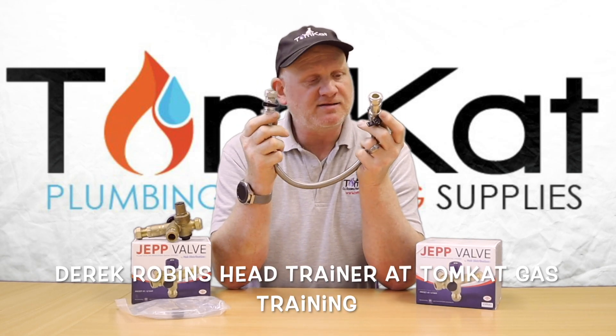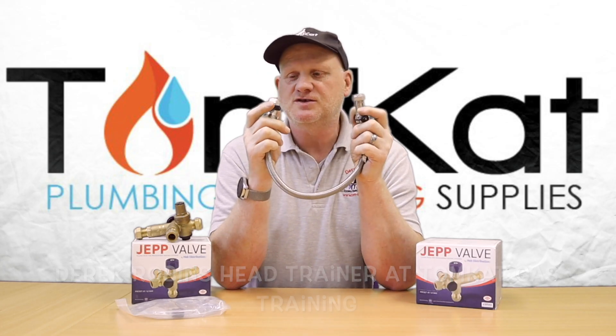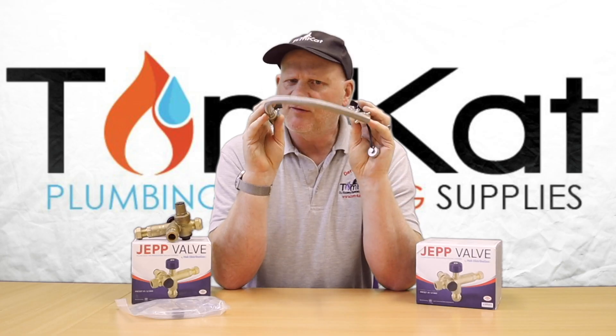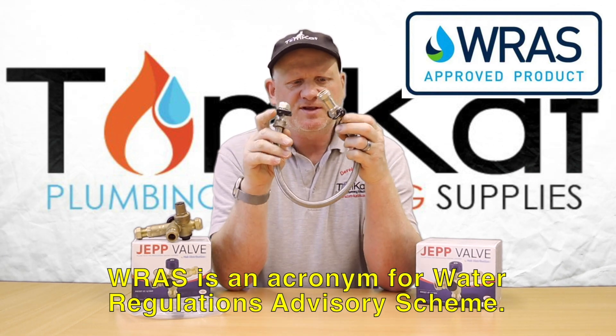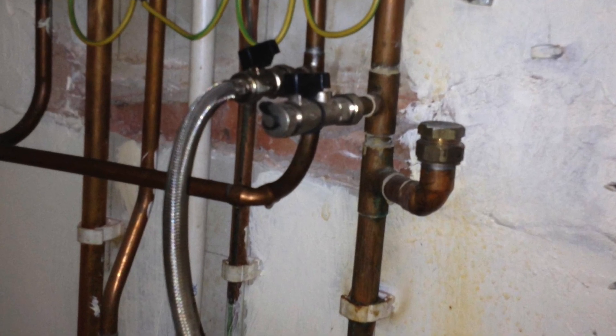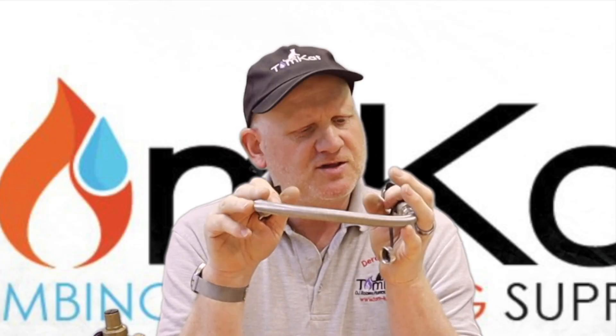This is a standard filling loop, which can be bought at any plumbers merchants and is basically used to fill central heating systems - sealed systems. But there are a couple of flaws with this. Even though this system is WRAS approved, we still need to disconnect the filling link after we've filled the central heating system, otherwise we're not complying with the water authorities regulations. Worst case scenario, we could get central heating water being sucked into our drinking water.